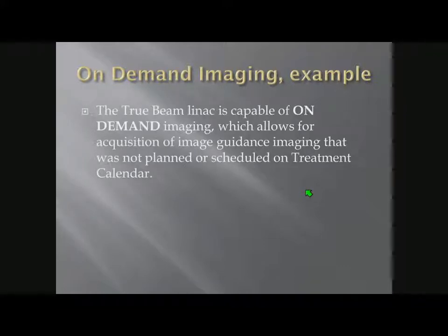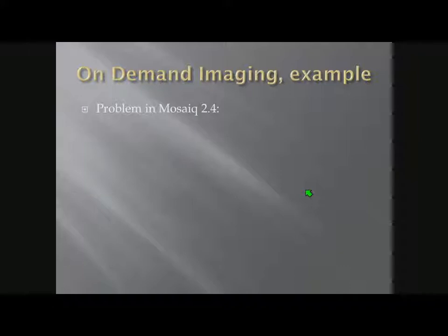The TrueBeam LINAC is capable of something called on-demand imaging, which allows for acquisition of image guidance imaging that was not planned or scheduled on the treatment calendar. The physician may show up today and say, hey, I want to get a cone beam CT. It's on-the-fly imaging at the machine. On-demand supports that. We happen to be at Mosaiq version 2.4. Version 2.62 is the most recent version, and we'll be upgrading to that shortly.